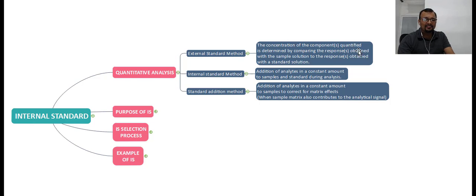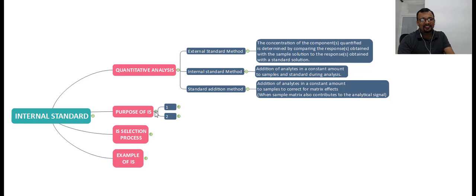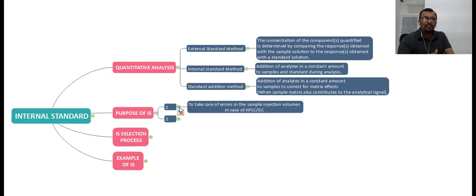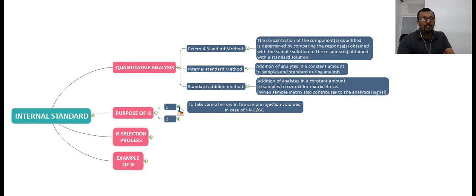Let us discuss in detail about the internal standard method — what is the purpose of an internal standard and why it is used. The first purpose is to take care of errors in sample injection volumes in the case of HPLC or gas chromatography. If there are injection-to-injection variations, it is not a fault of the standard or sample preparation process, but because of instrumentation errors in injections you may get variations in the end result, and hence to avoid these variations you can use an internal standard.